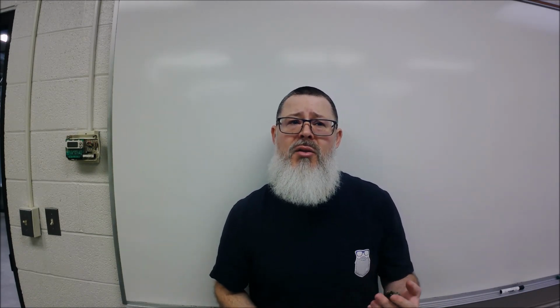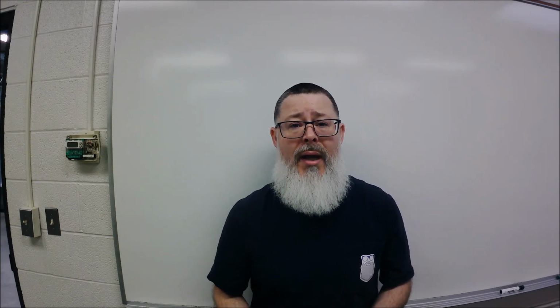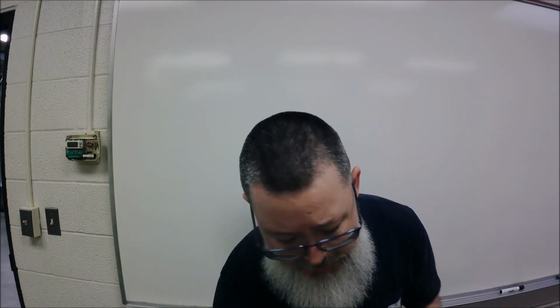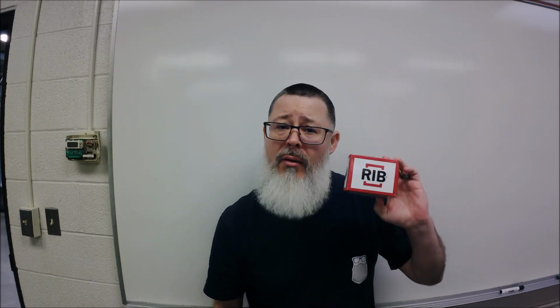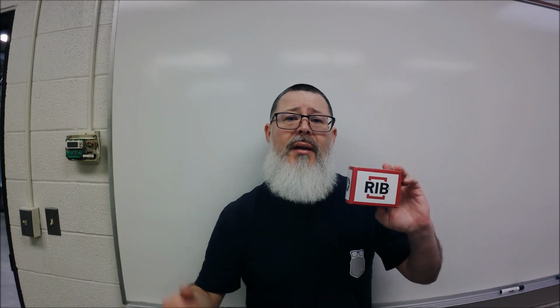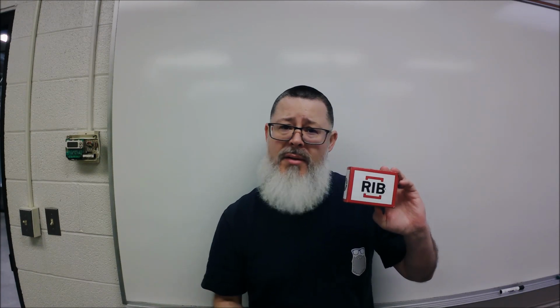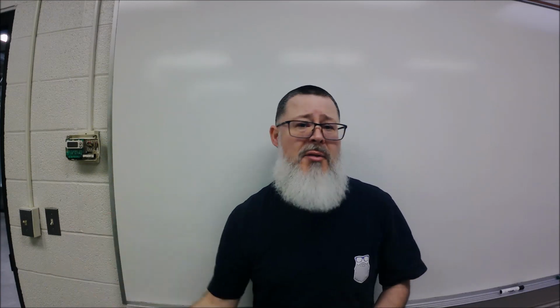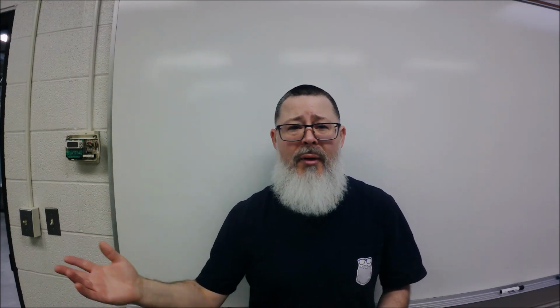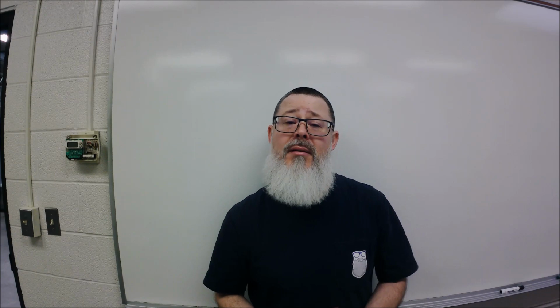Here lately, there's been talk about more commercialized controls. So what I'm going to do today is put a commercial type control in a residential air handler. This air handler's been wired and rewired, and I actually took it and resurrected it before, and we got rid of it, and now it's come back again because it serves a good purpose.